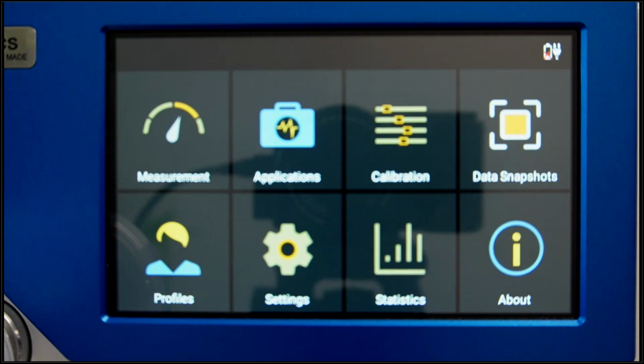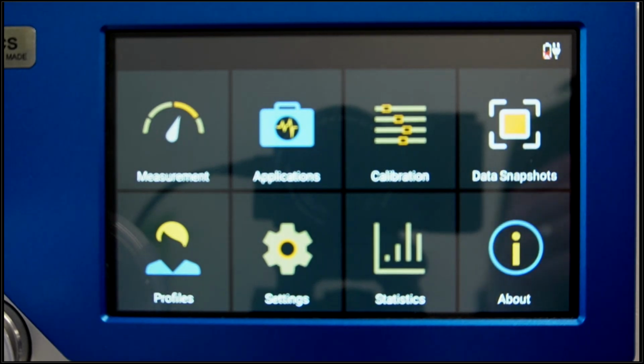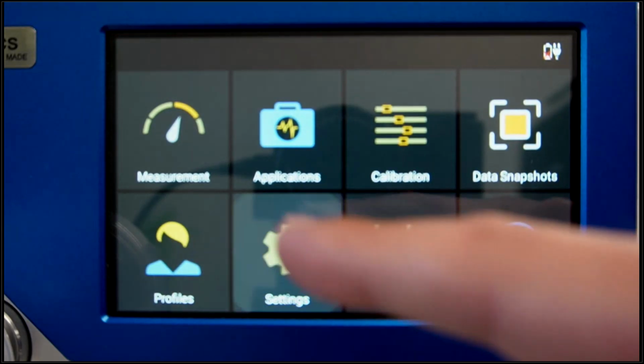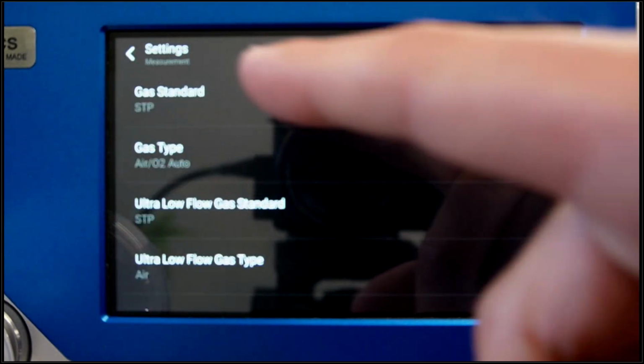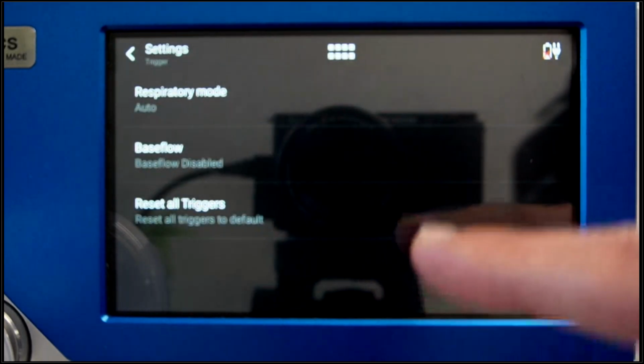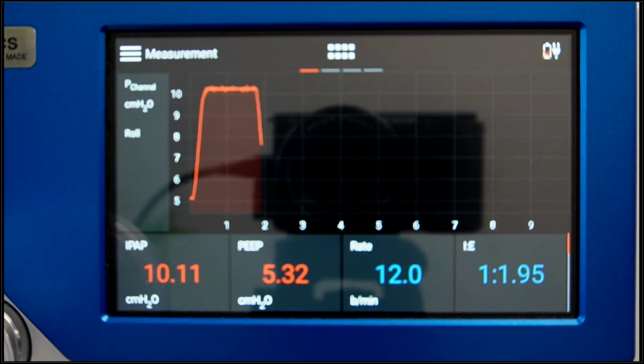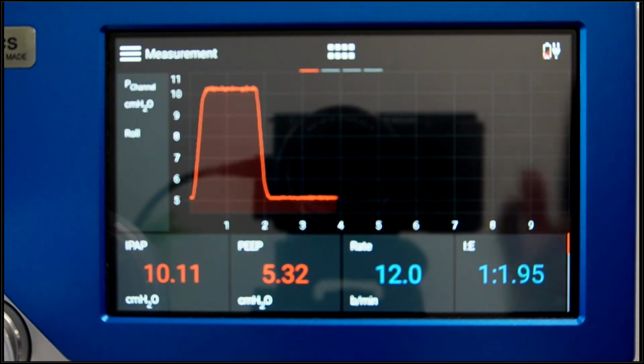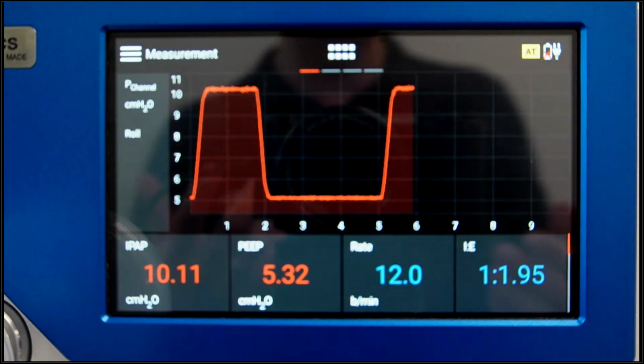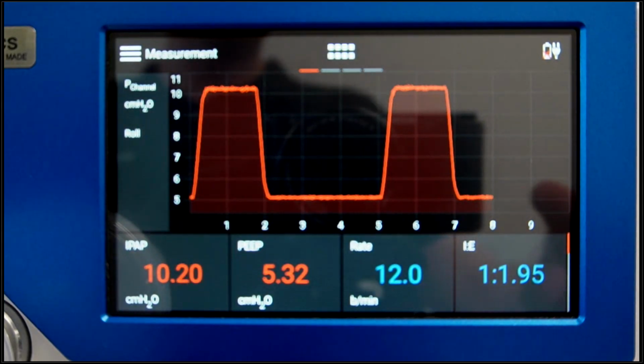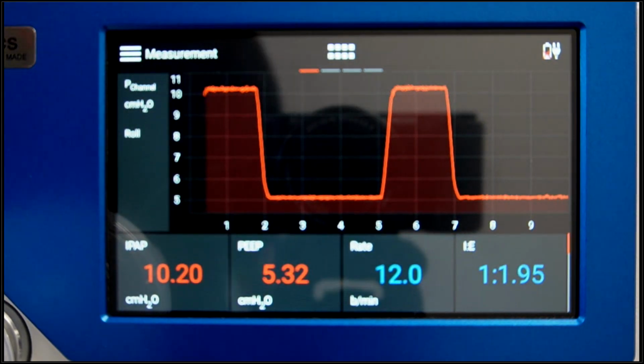And last but not least, on this device here, on our Flow Analyzer Pro, we also have something called automatic trigger detection. So what I can do here is I can set my whole trigger setting to be completely automated. So what the device is doing now is it analyzes the pressure and flow waveform in real time and finds suitable trigger settings for me. So as you can see, it's triggering now with my current settings.